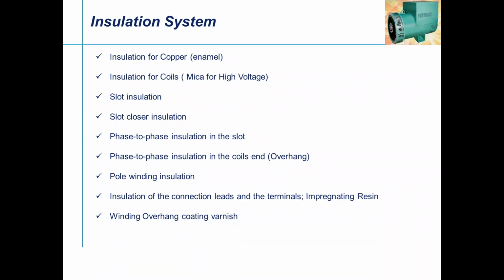Phase-to-phase insulation, the coil in the overhang. That means when the winding has been formed, there is also one more insulation on the overhang. And pole winding insulation: this is the main rotor where each pole will have an insulation provided, which is very, very important. It is like our skin, which safeguards our inner skin from other things. Just like our layer of skin is created, insulation is very important for the generator.